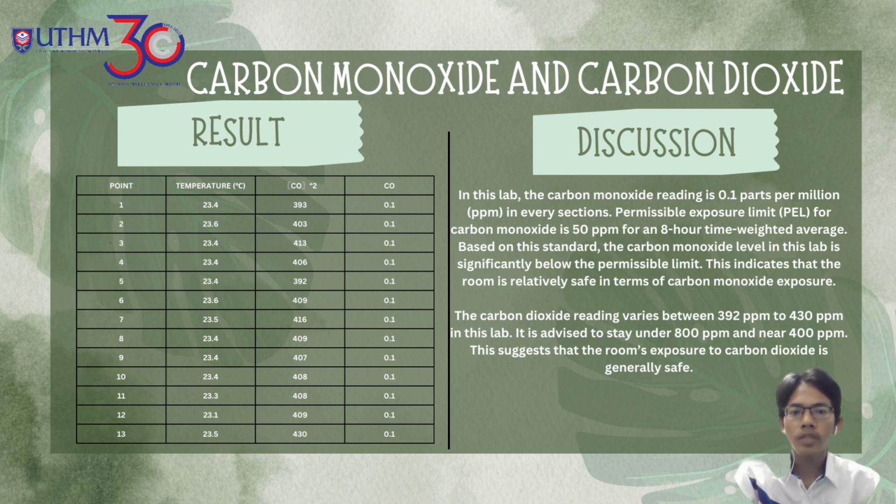The carbon dioxide reading varies between 392 ppm to 430 ppm in this lab. It is advised to stay under 800 ppm and near 400 ppm. This suggests that the room exposure to carbon dioxide is generally safe.